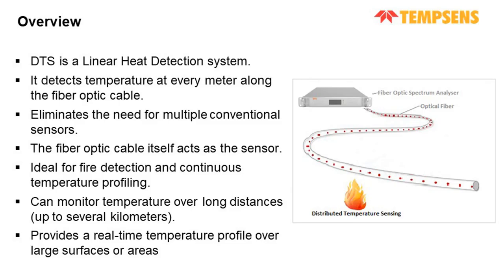What is remarkable is that the fiber itself is the sensor. You don't have to make any gratings, or add any additional sensor to it. Simple fibers can be used as a sensor. Then the second point is there is no need to install dozens or hundreds of individual sensing points. So this technology is especially used for applications like fire detection and long distance temperature monitoring.